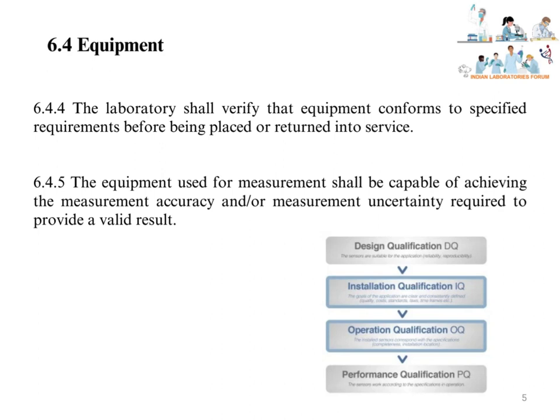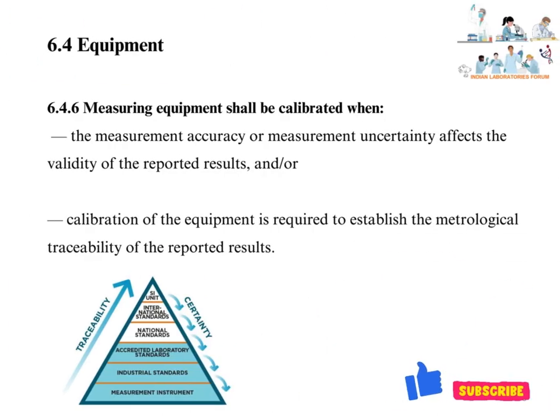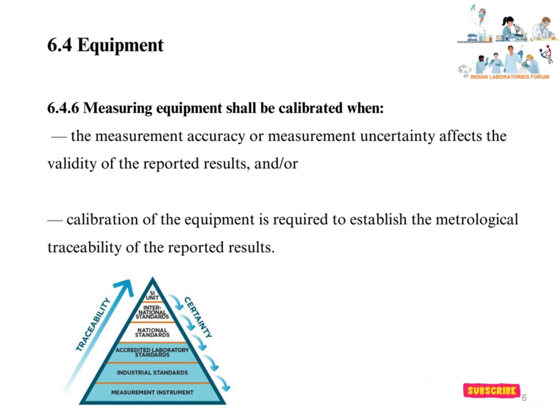Equipment used for measurement shall be capable of achieving the measurement accuracy and/or measurement uncertainty required to provide a valid result. The laboratory has to ensure that equipment used in the lab is capable of achieving the required accuracy — the closeness of the measured value to a standard or true value — and measurement uncertainty. Measuring equipment shall be calibrated when measurement accuracy or uncertainty affects the validity of reported results, or when calibration is required to establish metrological traceability.